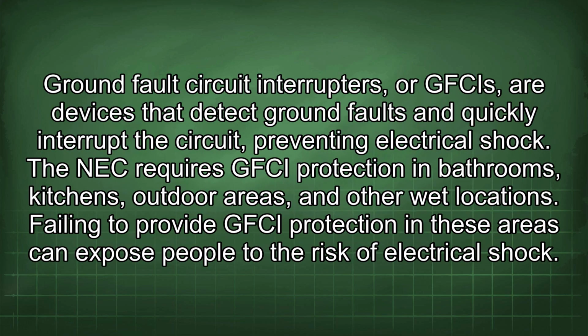Eighthly, GFCI protection is essential in wet locations. Ground fault circuit interrupters, or GFCIs, are devices that detect ground faults and quickly interrupt the circuit, preventing electrical shock. The NEC requires GFCI protection in bathrooms, kitchens, outdoor areas, and other wet locations. Failing to provide GFCI protection in these areas can expose people to the risk of electrical shock.